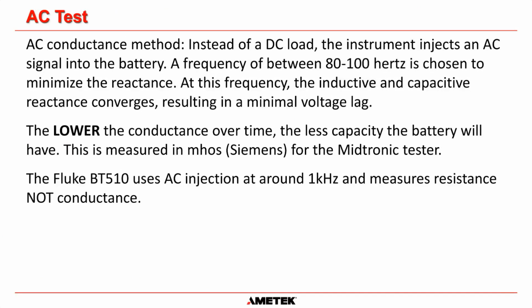Okay. For the other types of tests is the AC test. This top paragraph is taken from the Midtronics manual. But basically it says, instead of a DC load, the instrument injects an AC signal into the battery. So it's not putting a load on the battery, it's actually injecting an AC signal into the battery. And for the Midtronics, the frequency of that signal is between 80 to 100 hertz. And that's because at that frequency, the inductive and capacitive reactance meet together, they converge, resulting in a minimal voltage lag.